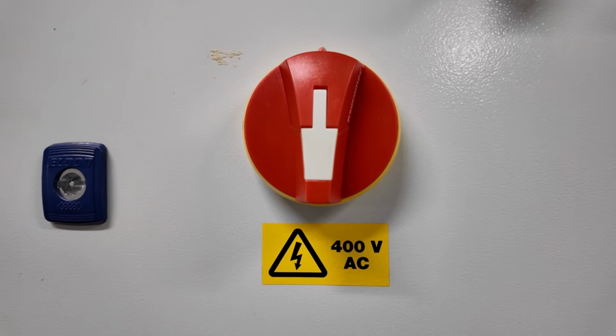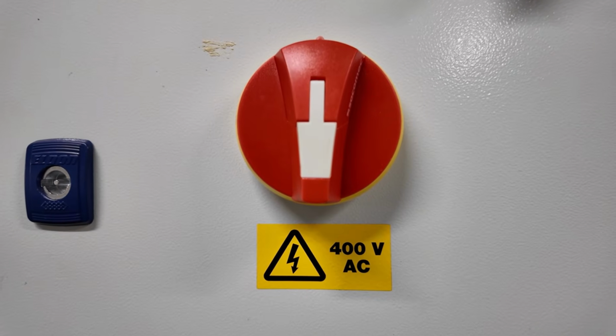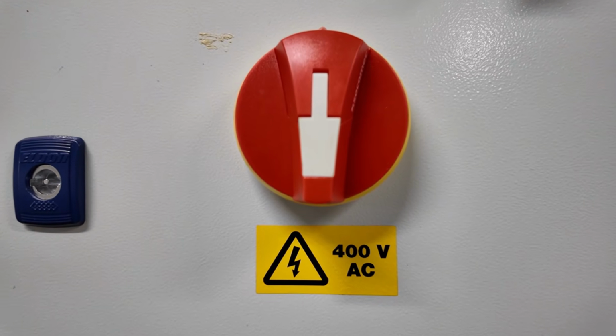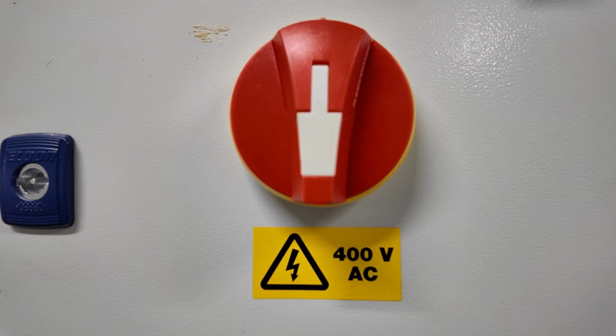Isolation is the foundation of electrical safety. Before work begins, fuses must be removed or circuit breakers opened to ensure all circuits are completely dead. Switches and circuit breakers should be locked open whenever possible. The person working on the system must maintain personal control over these isolation points.